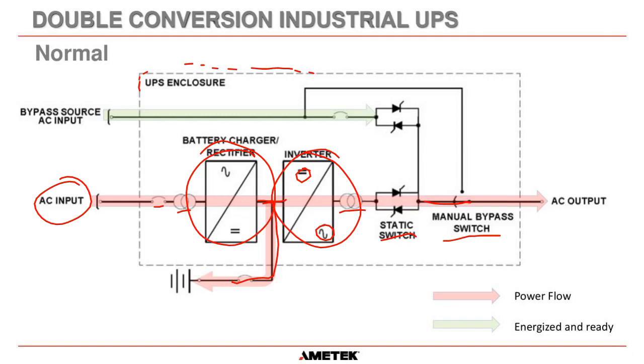Now, I always want to take the time to differentiate between the static switch and the manual bypass switch. The static switch is exactly as it is drawn here. There are 2 SCRs back to back in a static switch, and it is an electronic switch that has no moving parts in it, hence the reason it is called a static switch, as in there is no movement. So we can send a signal to these SCRs, and those SCRs will switch on instantaneously, and there is no waiting time for a contact moving from one position to another. The switch switches on instantaneously, very, very quickly indeed. And the benefit of there being no moving parts is there's no arcing between the contacts. So it's a very reliable electronic switch, okay?